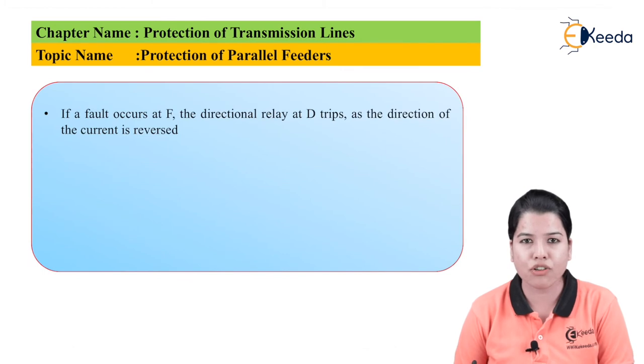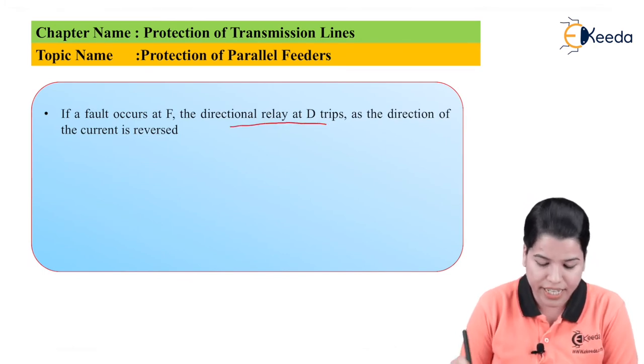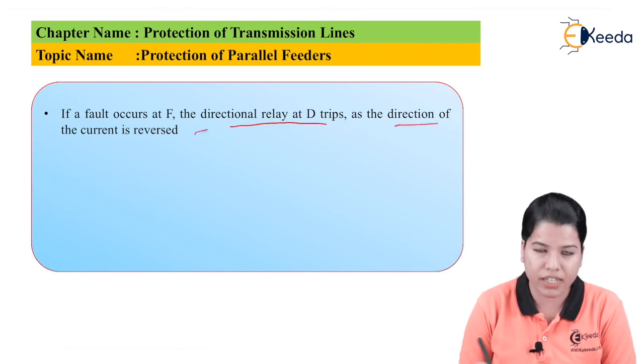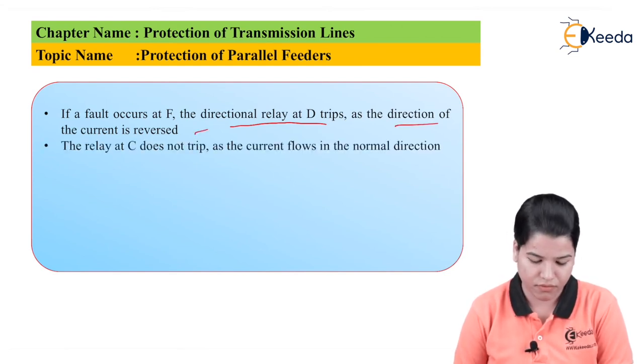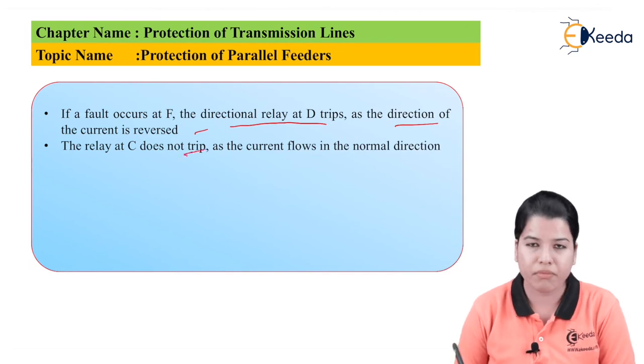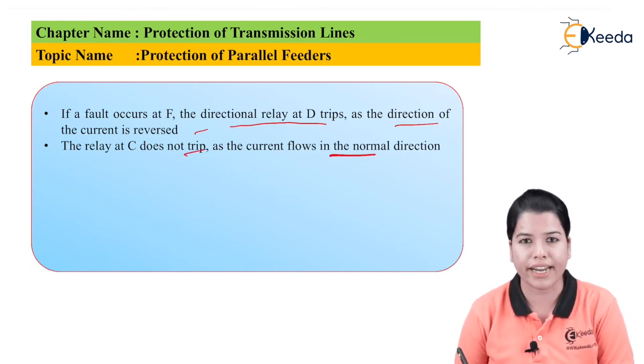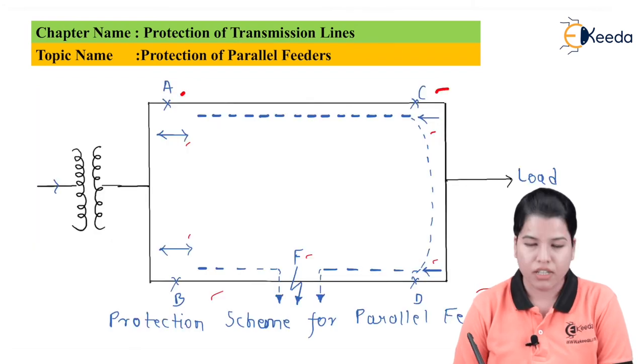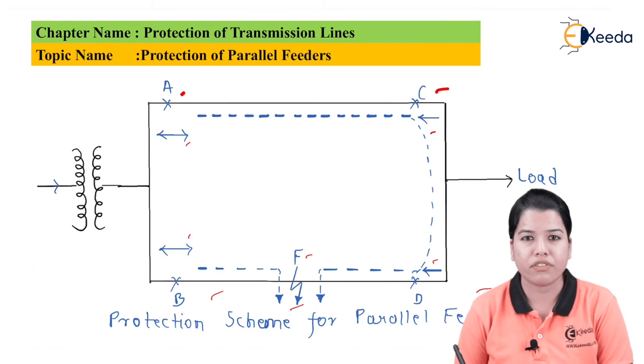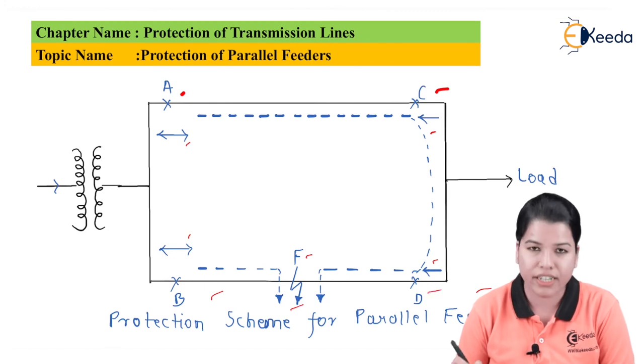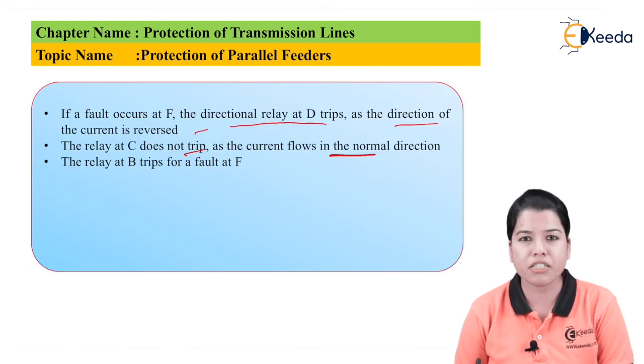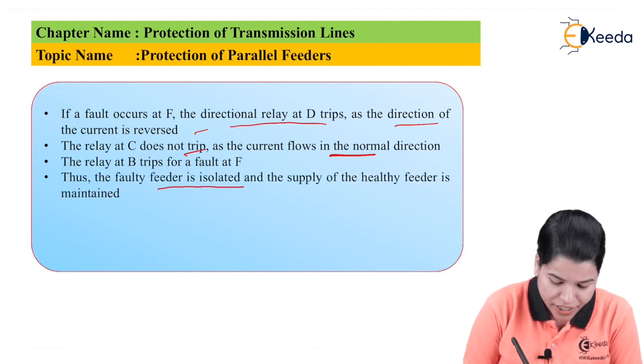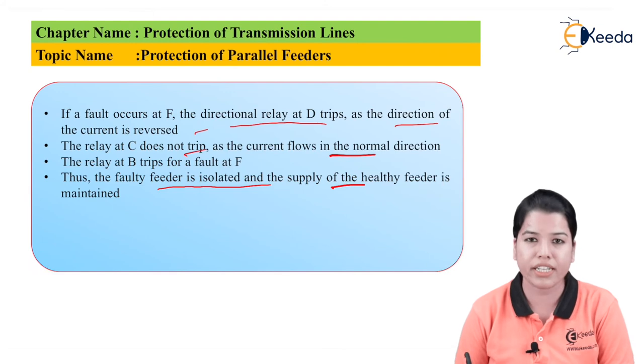Let us consider that a fault has occurred at point F. The directional relay at D will trip as the direction of the current is reversed. The relay at C does not trip as the current flow is in the normal direction. The relay present at B will also trip for the fault F. Thus, the faulty feeder will be isolated and the supply of the healthy feeder is maintained.